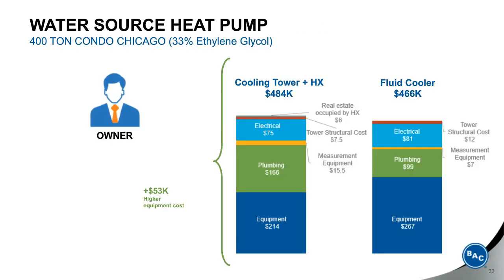So again, let's do another deep dive, this time on the 400-ton condo in Chicago, which used 33% ethylene glycol in the cooling loop. For the fluid cooler, which is shown on the right, at $466,000 total installed cost. The cooling tower heat exchanger, shown on the left, at a cost of $484,000. But again, you notice that the equipment costs, which is just the heat exchangers and either cooling tower or fluid cooler, showed an increase of $53,000 for the fluid cooler.